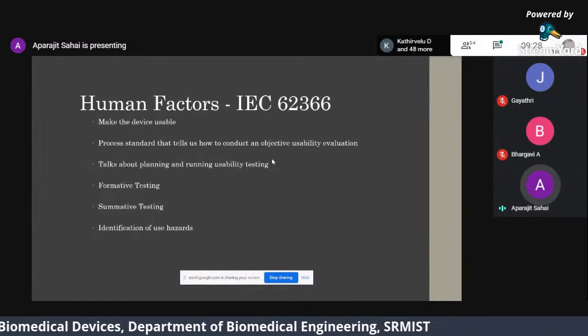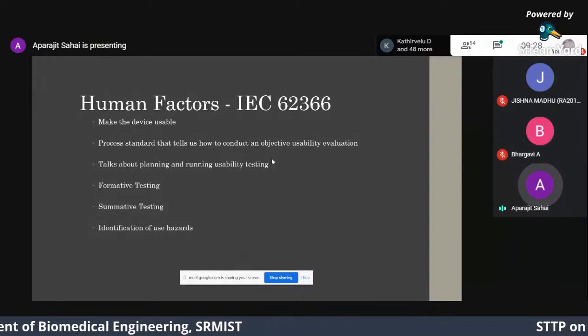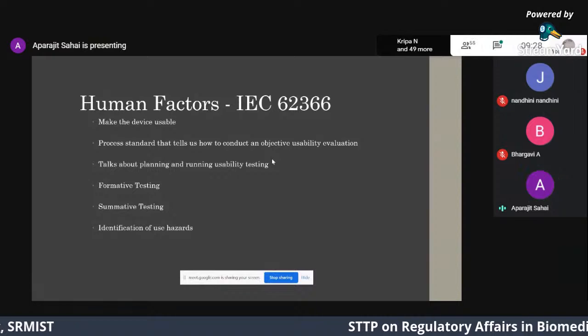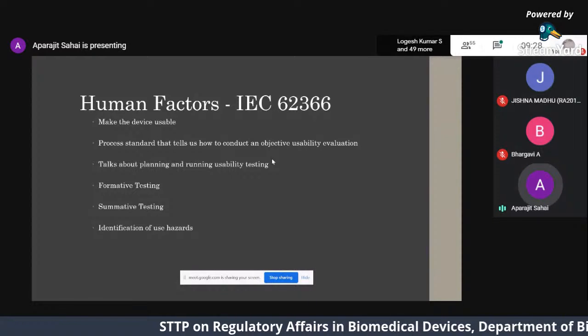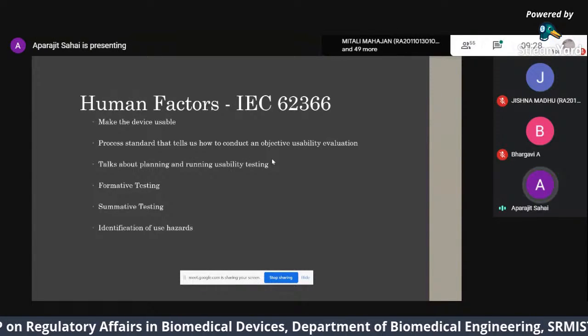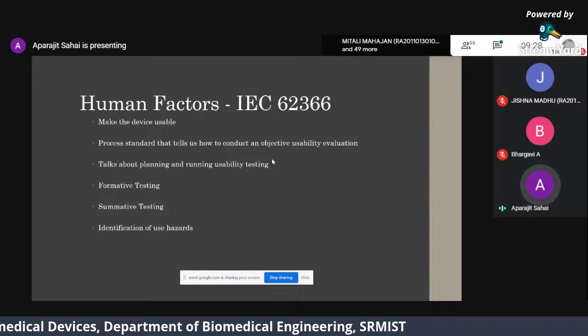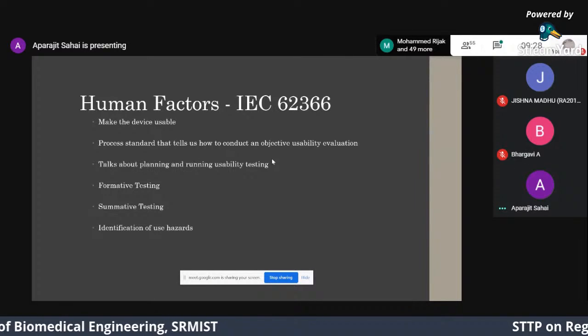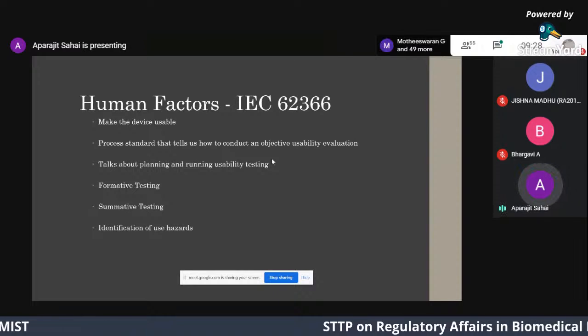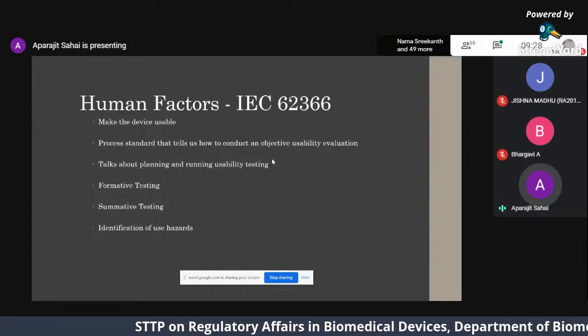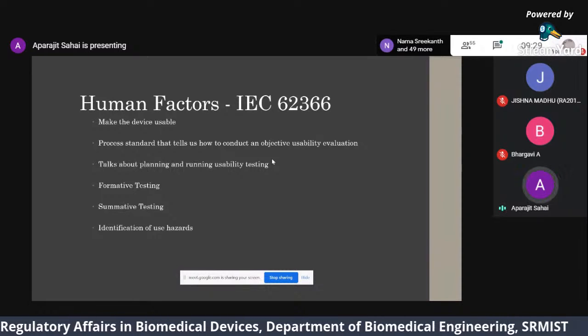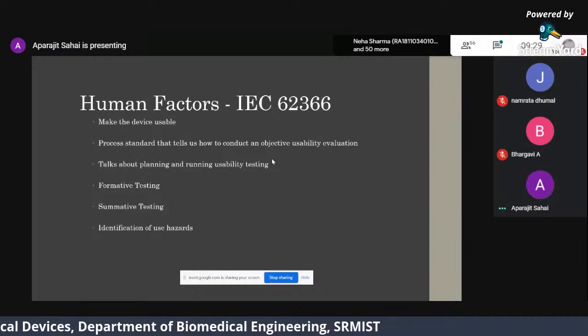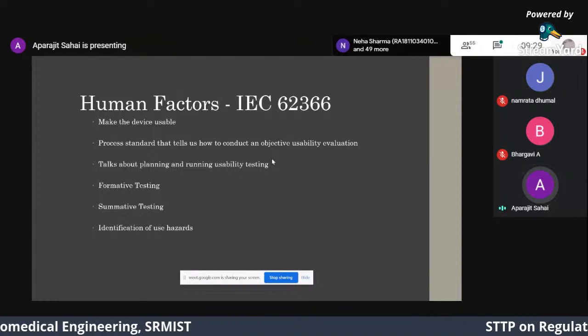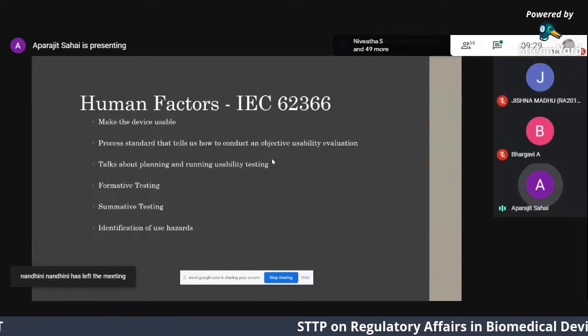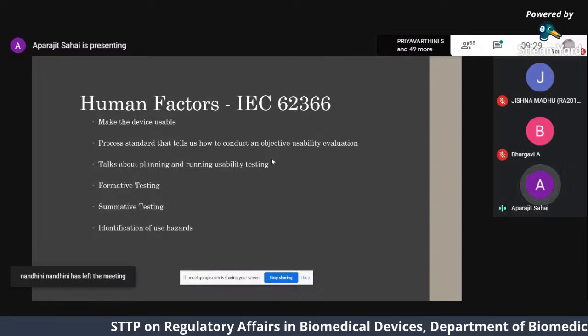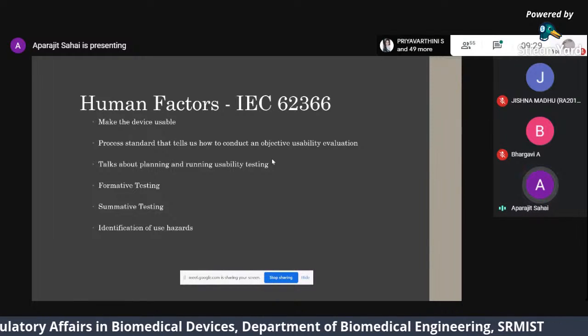Formative testing is when you're in the process of developing the device. You have some prototypes that you've come up with. So let's say you're thinking about three different kinds of designs which could potentially solve the problem you're trying to solve. You can go out to potential users, get their feedback on which of those would be most usable, which of those they like the most. That would be formative testing, and that would inform your design as it's being developed. But once your design is ready and you're ready to commercialize it, you do summative testing to make sure that the design meets all the marketing requirements and is in fact usable. That would be a final testing before you submit. You would submit both, but generally for low risk devices, you would just submit the summative testing for human factors to a regulatory body.